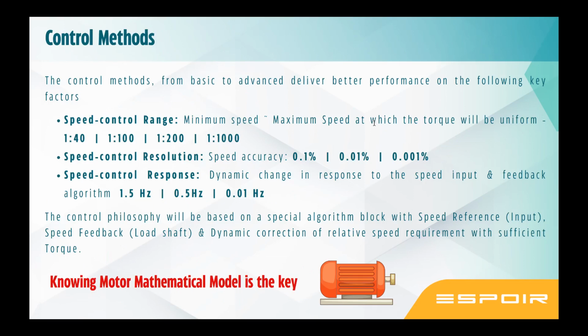You auto tune, so you go for an open loop sensorless vector control mode. Control the RPM as low as 14.5 RPM. Means you will achieve the required torque at as low as 15 RPM also. When you do a dynamic auto tuning, it does the rotation, it knows the motor parameters much better than the static auto tuner. So it gives you a better performance in terms of the speed control range.